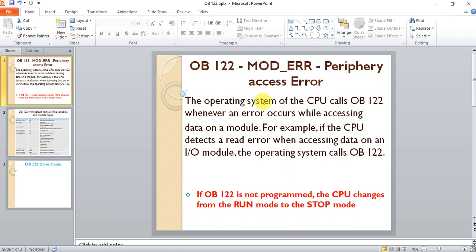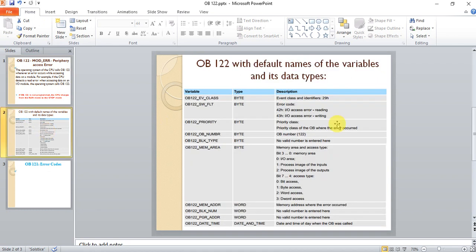For example, if the CPU detects a read error when accessing data on an IO module, the operating system calls OB122. So if OB122 is not programmed, the CPU changes from run mode to stop mode. Here are some default variables of OB122 that provide information or error codes for the fault.